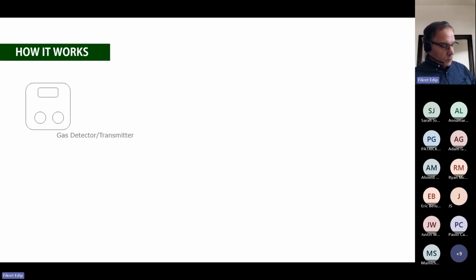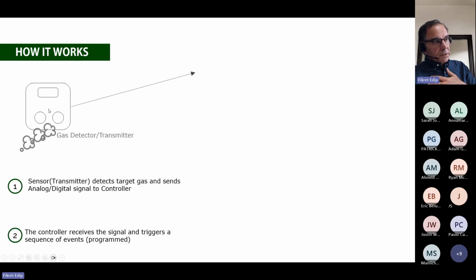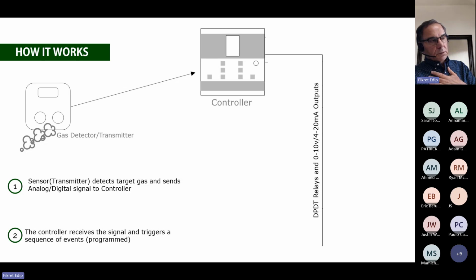It all starts from your transmitter, the gas detector or transmitter. Gas detectors are designed to detect the concentration of the leaked gas. Which gas? A target gas, whichever your target gas is: CO, NO2, propane, methane, you name it. The transmitter detects gas, and basically it just sends out a signal to a controller. This signal sent from the transmitter to the controller can be an analog signal, which is 4 to 20 milliamp or 0 to 10 volt. I'm not trying to get too technical here, but with 4 to 20 milliamp, if it's 4 milliamp going out to the controller, the controller says I am okay, I am safe.